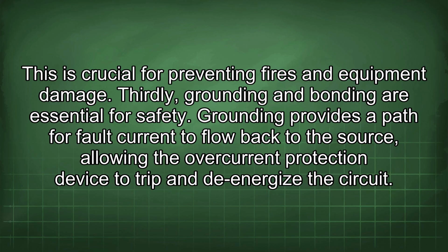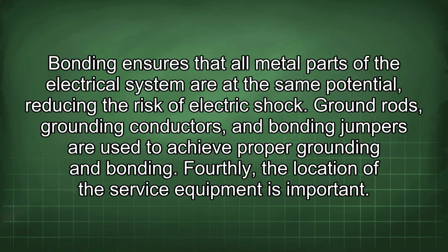Thirdly, grounding and bonding are essential for safety. Grounding provides a path for fault current to flow back to the source, allowing the overcurrent protection device to trip and de-energize the circuit. Bonding ensures that all metal parts of the electrical system are at the same potential, reducing the risk of electric shock. Ground rods, grounding conductors, and bonding jumpers are used to achieve proper grounding and bonding.